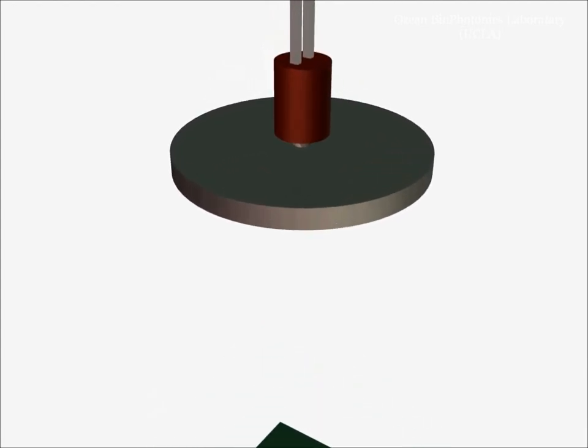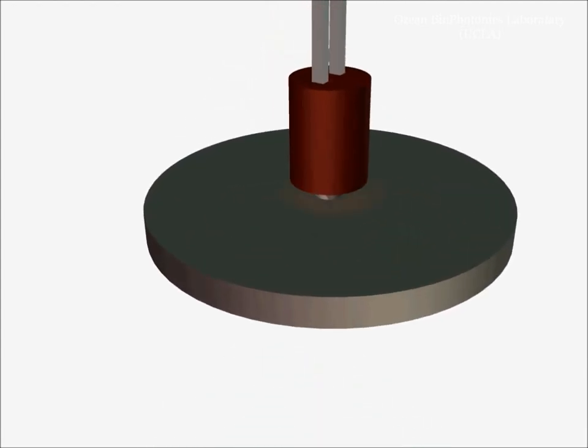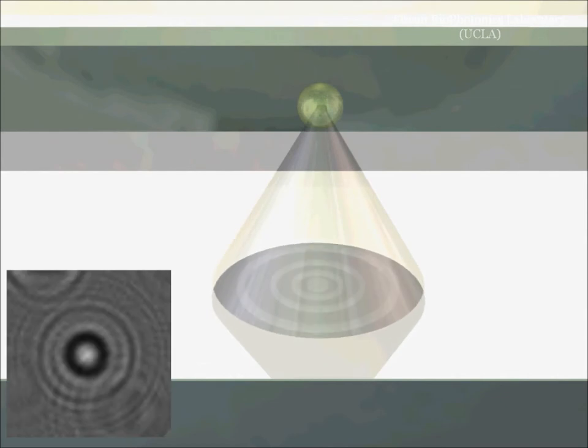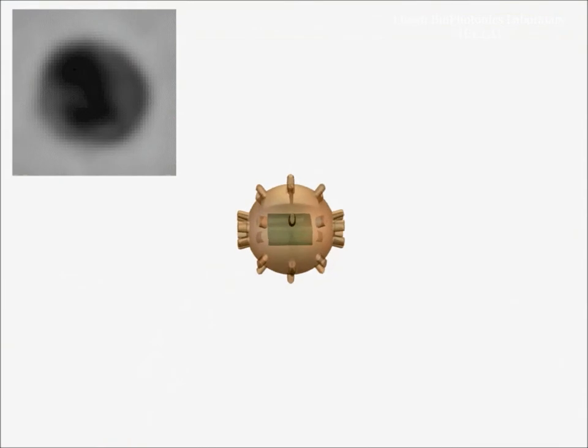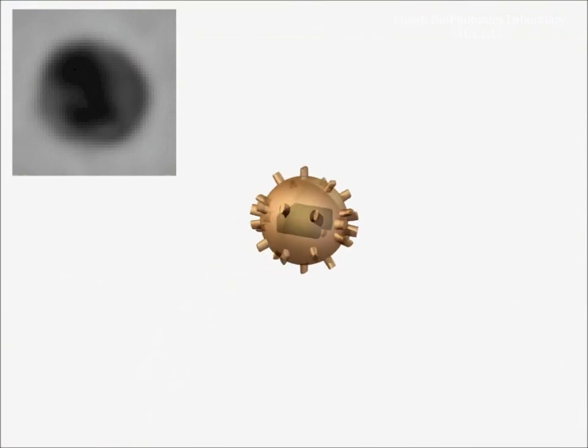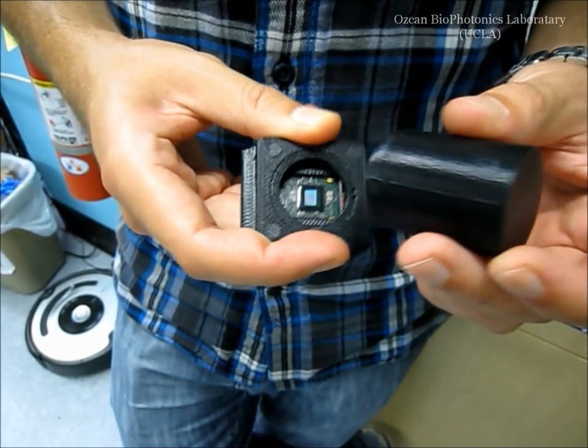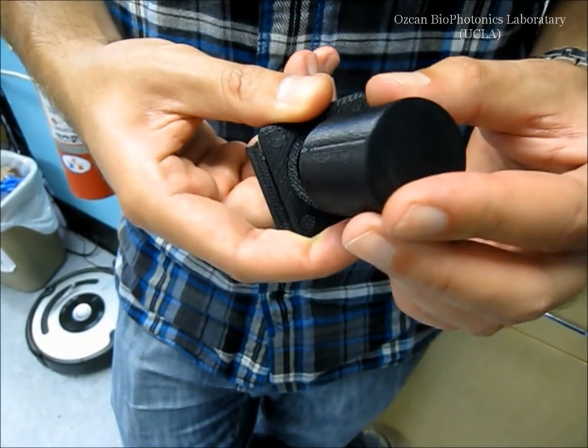A simple LED from the top of the lensless microscope illuminates the sample of interest. A CMOS sensor on the bottom of the microscope records the digital holograms of individual particles within the sample, which are basically unique for each type of a cell, bacteria, or parasite. We digitally process these raw holograms using our signal processing software to generate their microscope images.